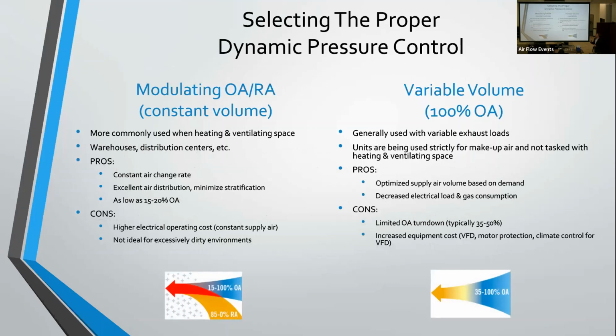Okay, so what are your options for dynamic pressure controls? There's two that we typically see. There's generally two that you look at. The first one would be a modulating outside air and return air unit, which operates at usually a constant air volume. And all you're doing is just modulating these linked outside air and return air dampers to vary the amount of outside air being delivered to the space. The other common option is a 100% outside air unit, so you're not recirculating any air back through the unit, and then you're varying the volume, typically done with the VFD.